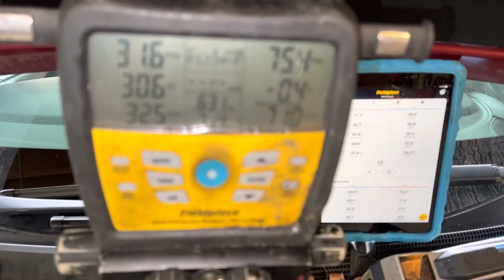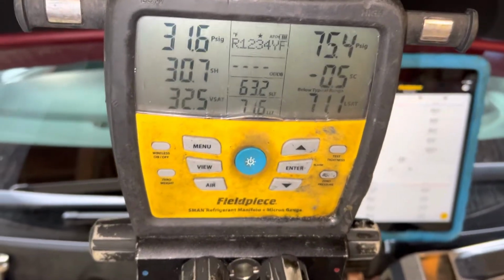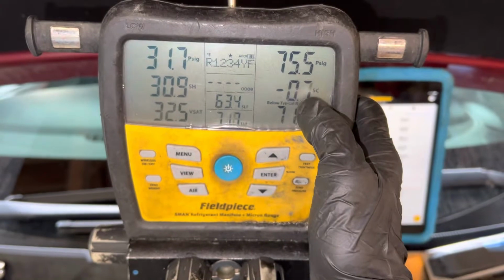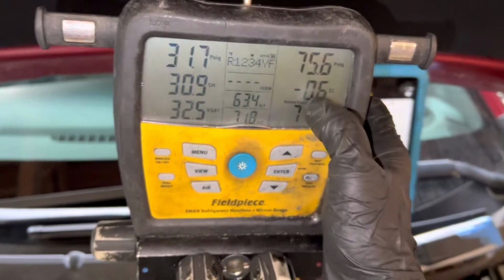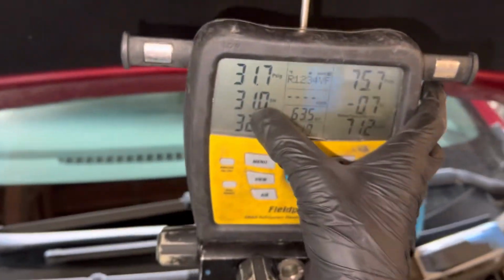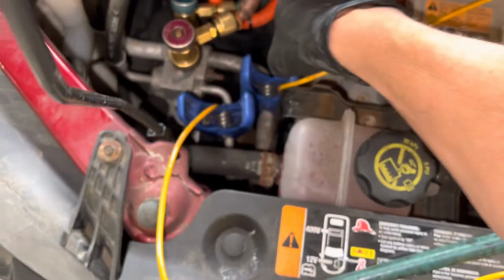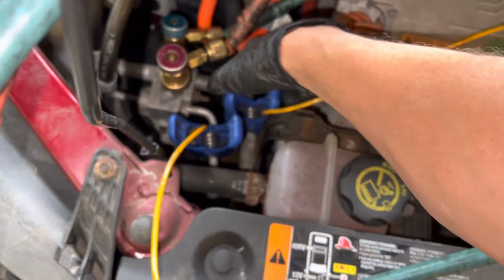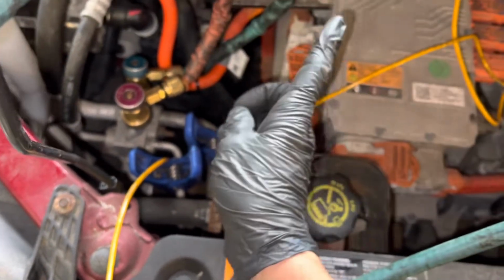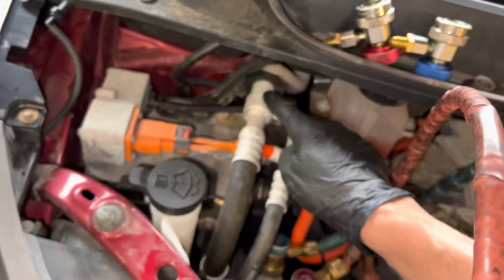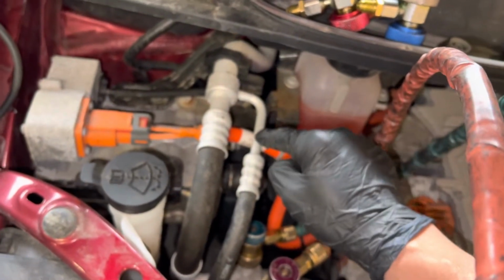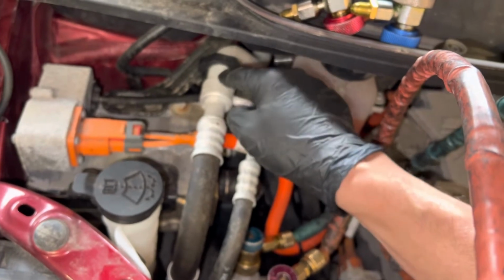We're sitting at 31 on the low side, 75 psi on the high side. And as you see, look at the subcooling. Subcooling is negative. You can't have negative subcooling. Look at the superheat. We're at 31. But I am taking the superheat down here towards the compressor, not at the evaporator up above. And we do have an internal heat exchanger. You see the liquid line going into the vapor line.